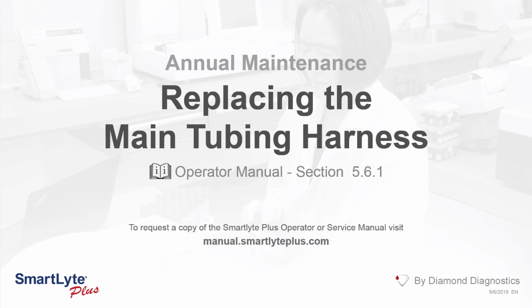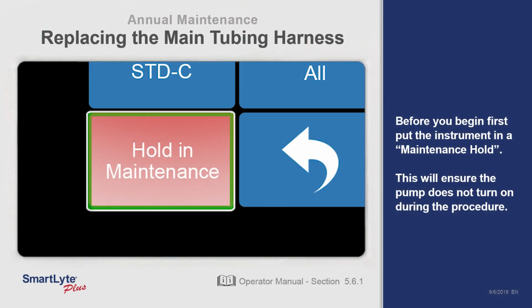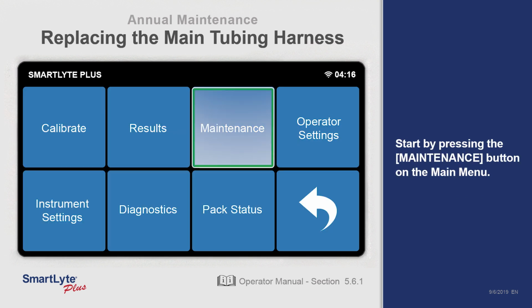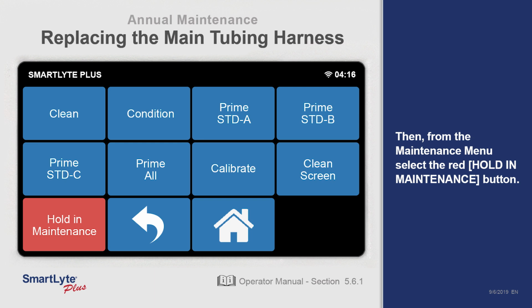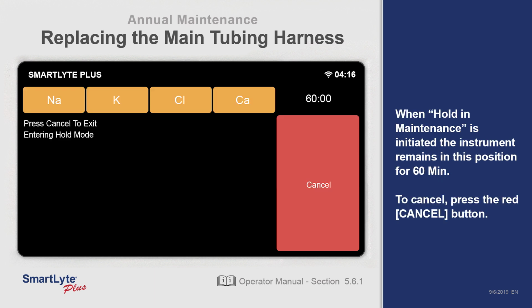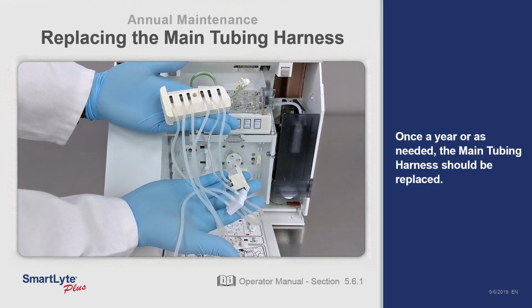Replacing the main tubing harness. Before you begin, first put the instrument in a maintenance hold. This will ensure that the pump does not turn on during the procedure. Start by pressing the maintenance button on the main menu. Then, from the maintenance menu, select the red Hold in Maintenance button. When hold in maintenance is initiated, the instrument remains in this position for 60 minutes. To cancel, press the red cancel button. Once a year, or as needed, the main tubing harness should be replaced.